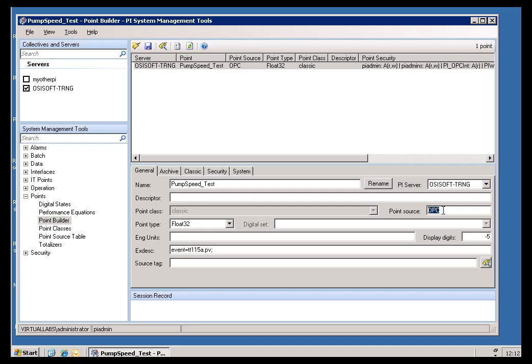At that point, when it sees that there are still more tags to be processed after the first 25, it will go ahead and check again 30 seconds later. Once it sees there's more to be done, it will go ahead and process every 30 seconds another 25 tags. That does mean that if there are thousands and thousands of tags you just added, it can take a while for all of those tags to be picked up by the Interface.